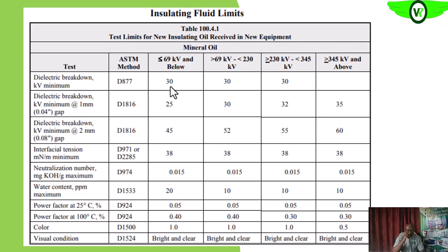So it should not break down below this voltage in kilovolts. Then the dielectric breakdown, if the distance between the electrodes is 1 mm, this is acceptable. If it is 2 mm, this is acceptable. Then the interfacial tension in Newton per meter should also not be below this. Then the neutralization number, that is the acid neutralization number. These are some of the recommended values.